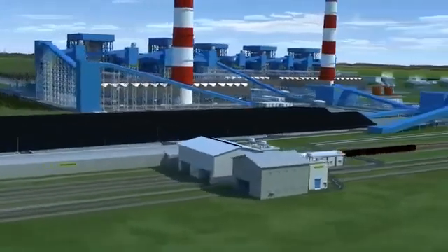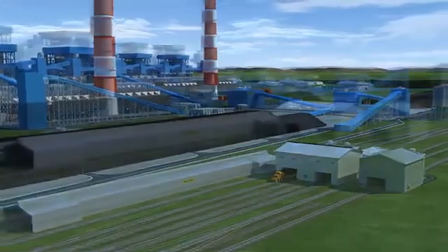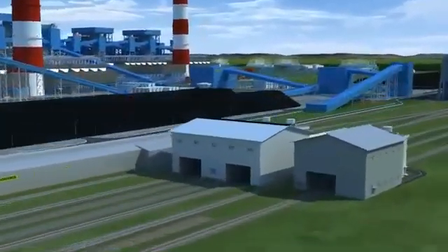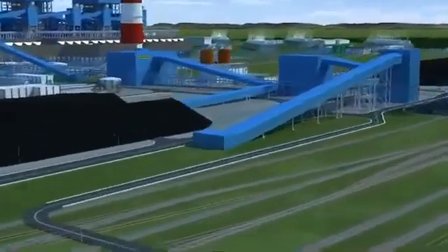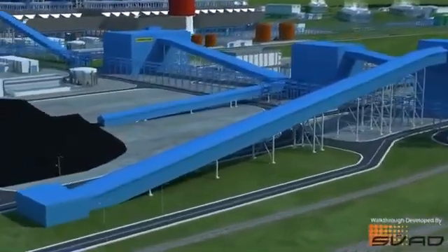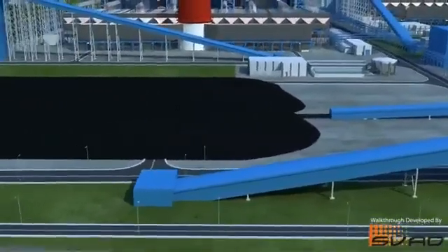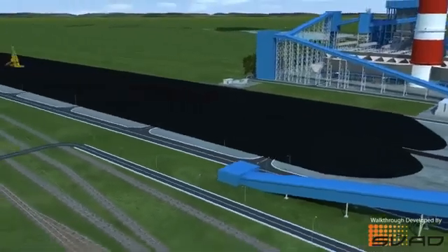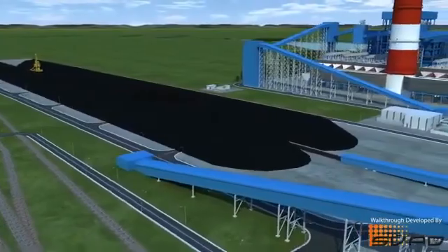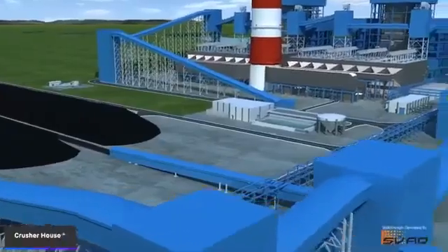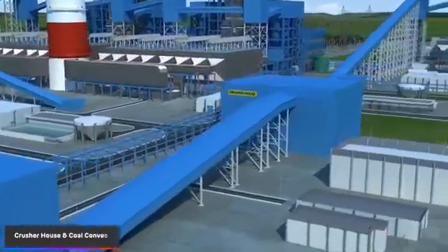The coal handling plant has been supplied by Messrs. Larsen & Toubro Limited. The coal will be unloaded through a track hopper and 4 numbers of wagon tipplers. The coal is then further conveyed either to the stockyards within the plant or to coal bunkers of various units. Facility to store around 7.2 lakh metric tons of coal, which is about 15 days stock, is made through 2 stockyards. Coal passes through 6 number of crushers, each of 1,250 tons per hour, installed in a single crusher house. The coal is fed to coal bunkers of different units before entering the milling system via coal feeders.